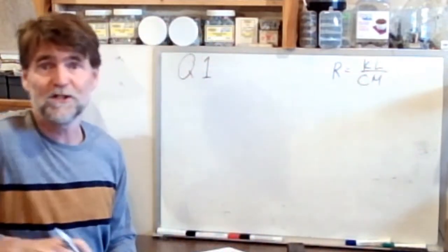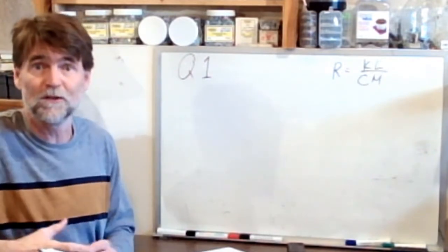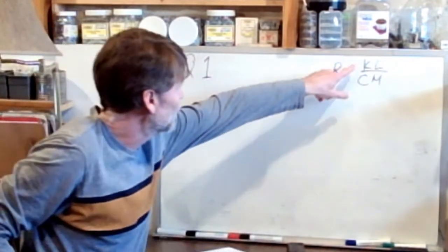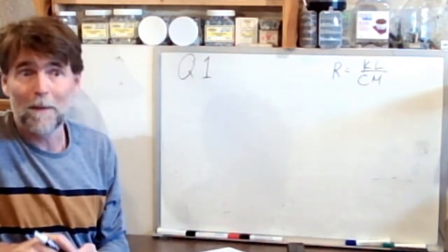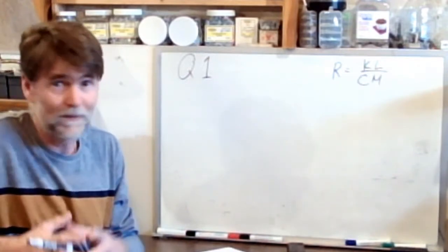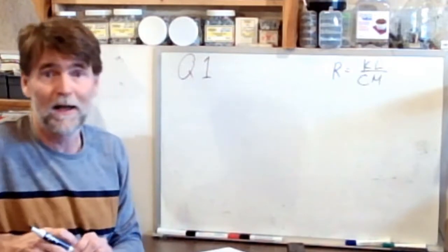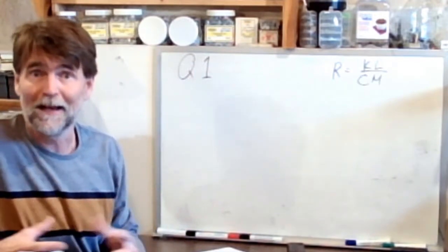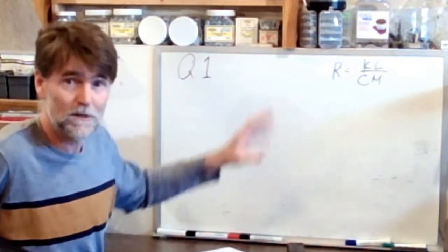Okay, so ultimately we have to plunk the right numbers into those variables. K is the specific resistance of the material that is the conductor. Length is the length of the conductor. Remember, in feet. This is all imperial stuff, not metric. And divided by the circular mil area of the conductor. Okay, so that's our equation.